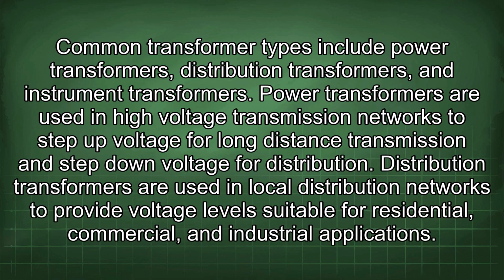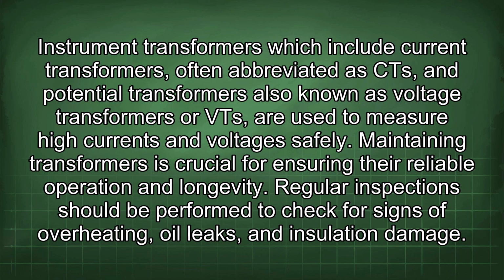Common transformer types include power transformers, distribution transformers, and instrument transformers. Power transformers are used in high-voltage transmission networks to step up voltage for long-distance transmission and step down voltage for distribution. Distribution transformers are used in local distribution networks to provide voltage levels suitable for residential, commercial, and industrial applications. Instrument transformers, which include current transformers, often abbreviated as CT, and potential transformers, also known as voltage transformers, or VT, are used to measure high currents and voltages safely.